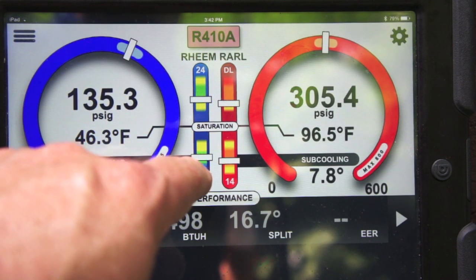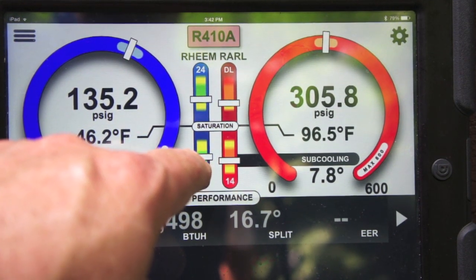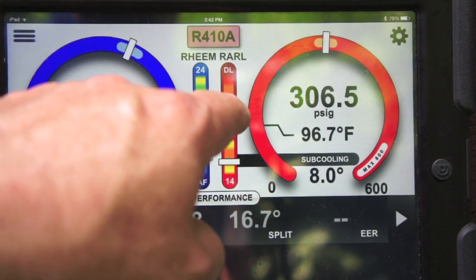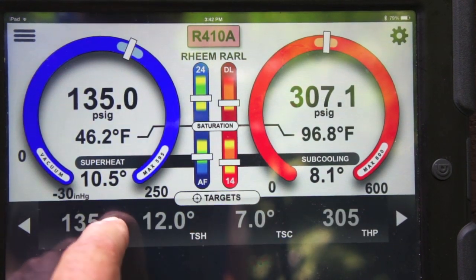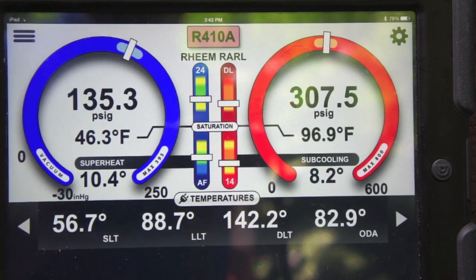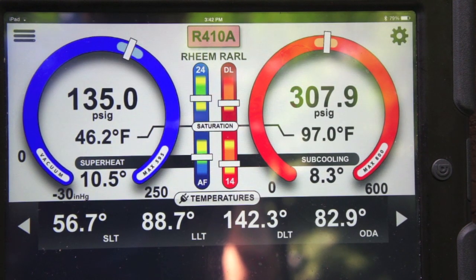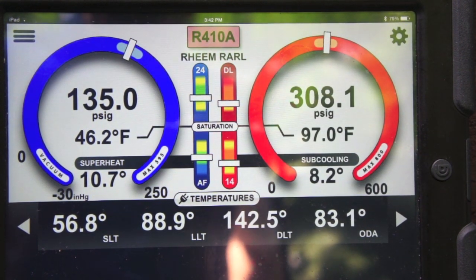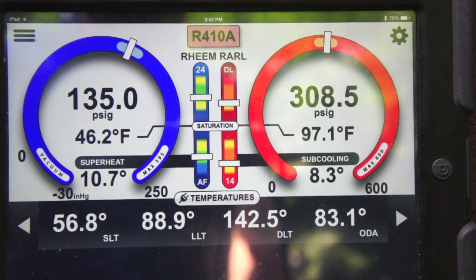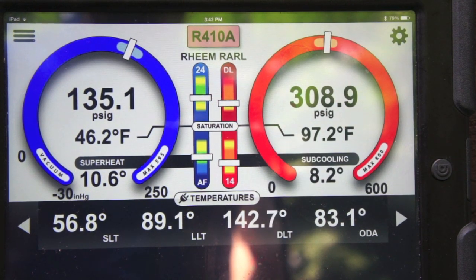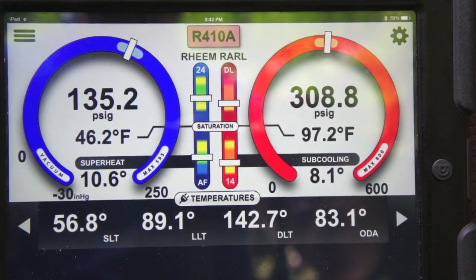We have plenty of airflow. It's right in the middle here, which means we're within 3 degrees of our split temperature. Our discharge line temperature is running about 142 degrees, and our superheat is running 10.5 degrees. Everything is right where it should be. So we're going to go ahead and get electrical measurements, and we'll finalize this thing and get it done.